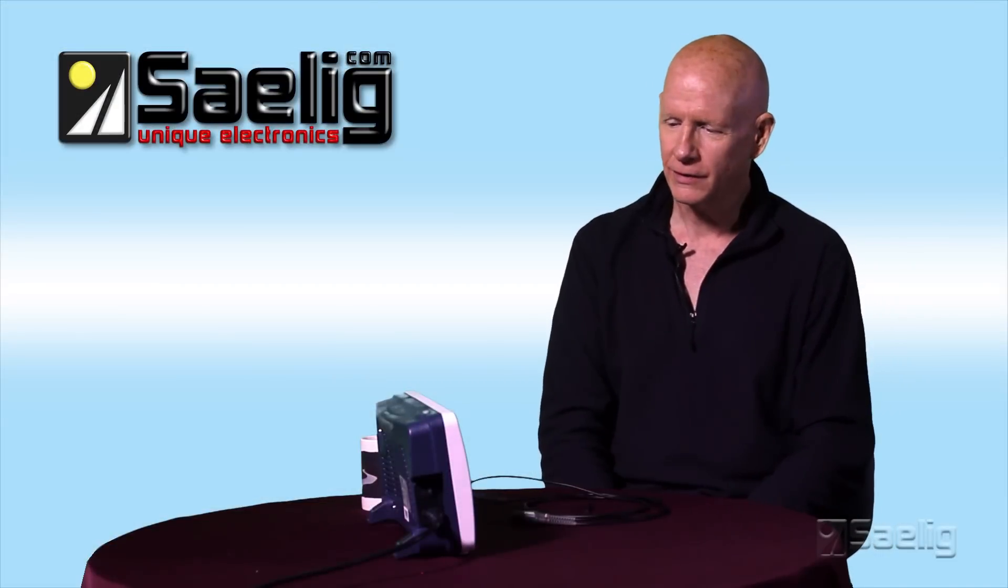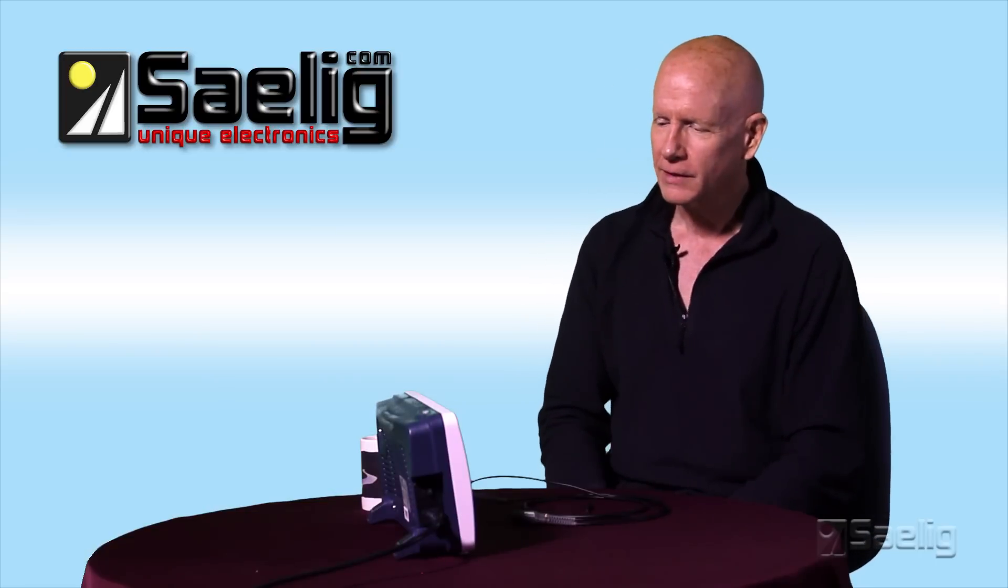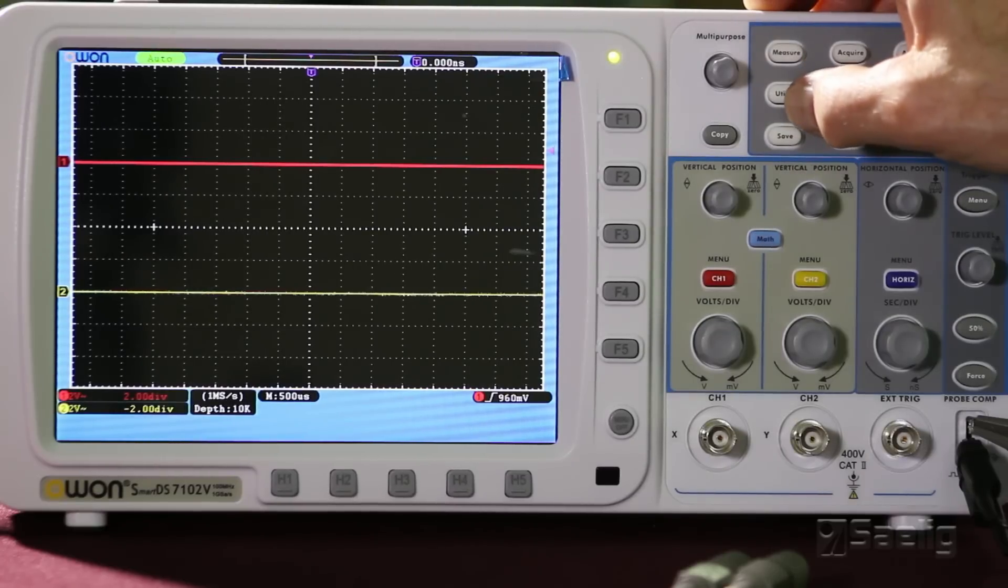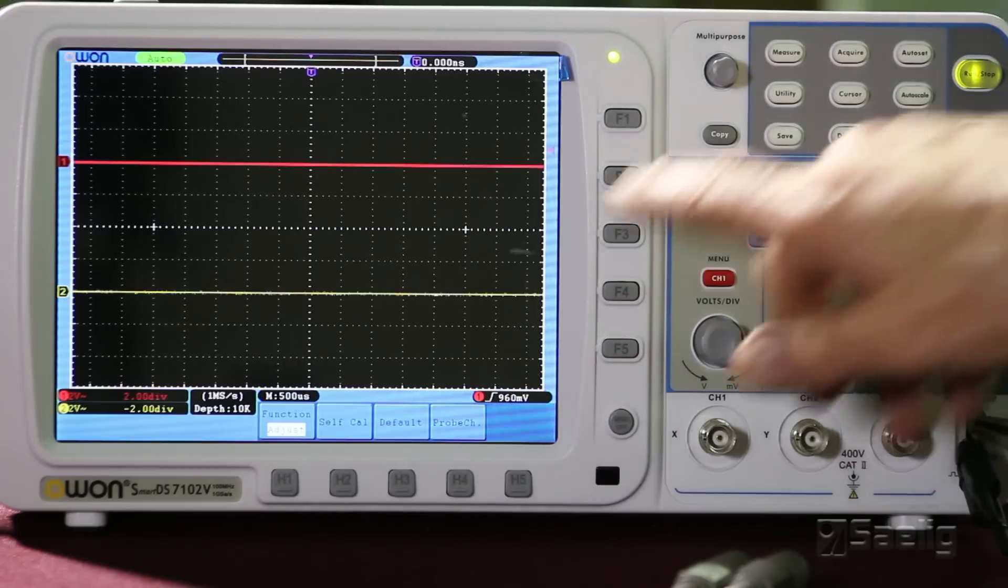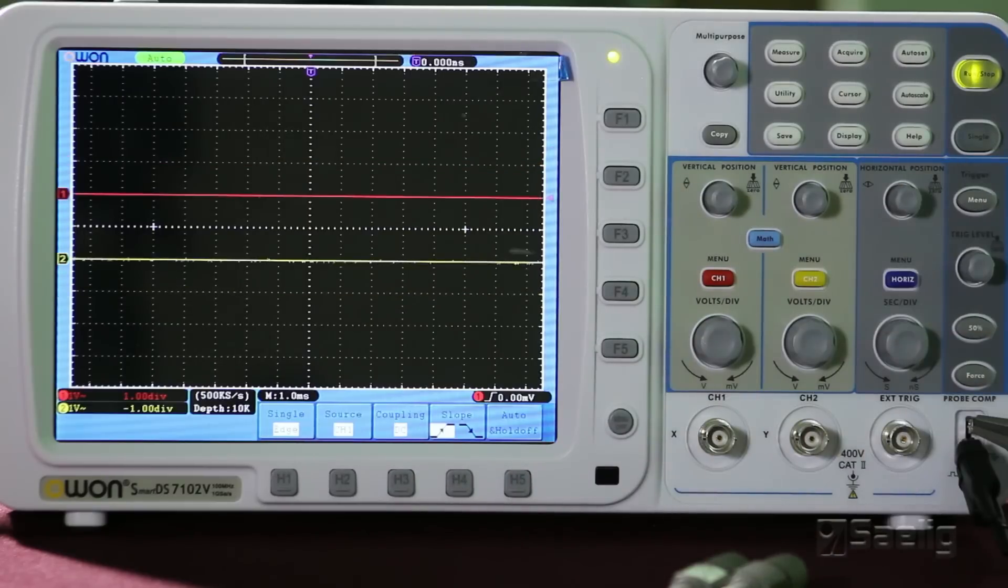So, the first thing we were going to do after we established that power on self-test was working properly, we were going to look and see if we could set factory defaults. Now, some scopes will have a default button, others will have it buried somewhere in the menus like this one does. This one has it under the utility key and I'm just going to hit defaults right here and get the scope to assume all the settings that it comes right out of the box.